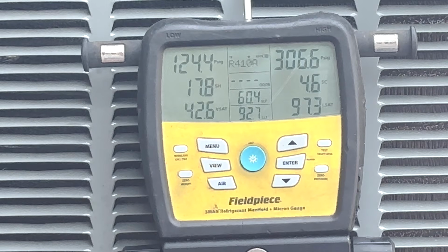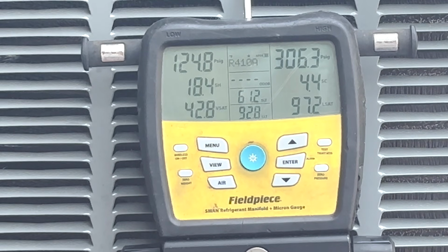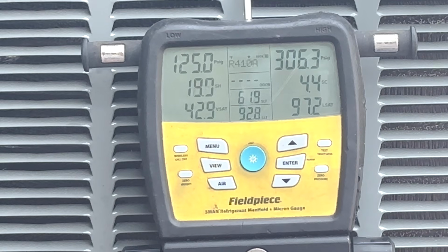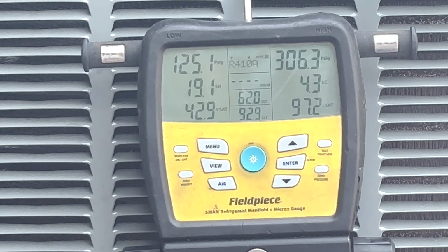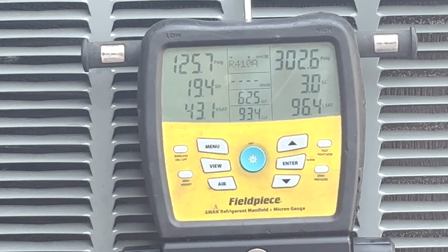The suction pressure and head pressure are not enough information to determine if it's a valve. It's not enough information to determine if it's non-condensables. The superheat and the subcool aren't even enough information if they're fluctuating. You're going to need all four of these values present to understand this diagnostic.